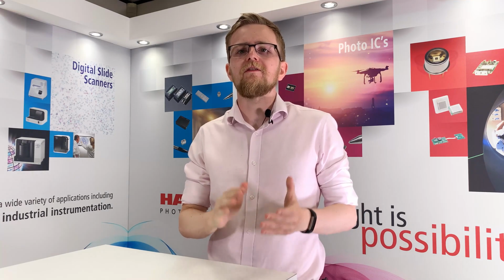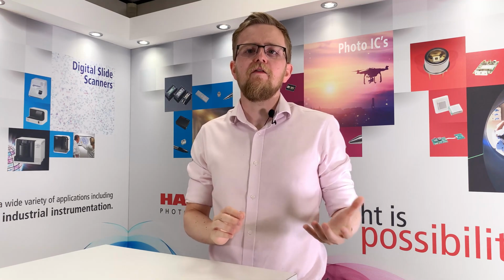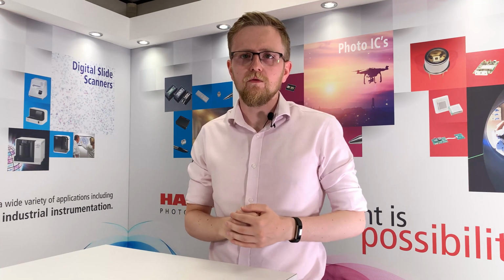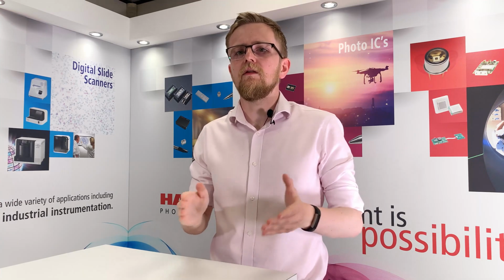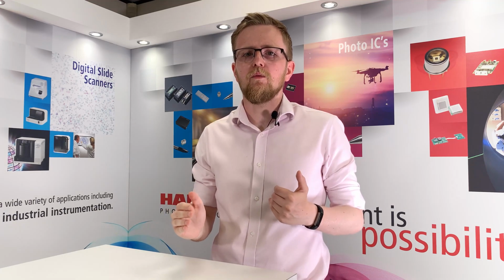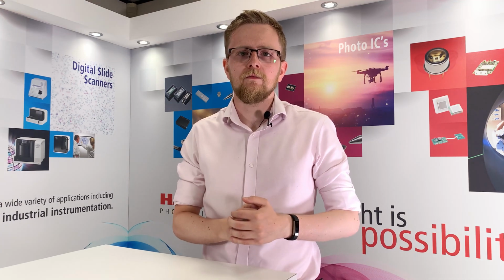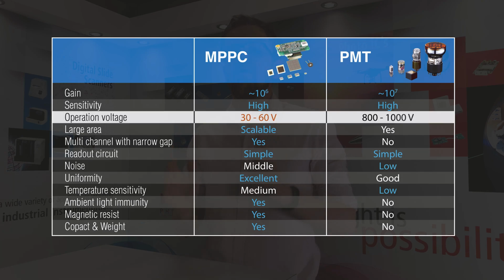PMTs are still unrivaled for applications that require very low light counts, because inherent noise in the silicon material means that PMTs have a much lower dark count and therefore can detect much smaller numbers of photons. They also provide a much larger wavelength response range, whereas the response range of silicon inherently limits SiPMs. However, for specific applications within that response range with mid to high light counts, such as for radiation detection, SiPMs can offer advantages. Firstly, PMTs require around 1000 volts to operate, which for portable devices can be an issue, whereas SiPMs operate in a range of around 35 to 60 volts depending on device type.